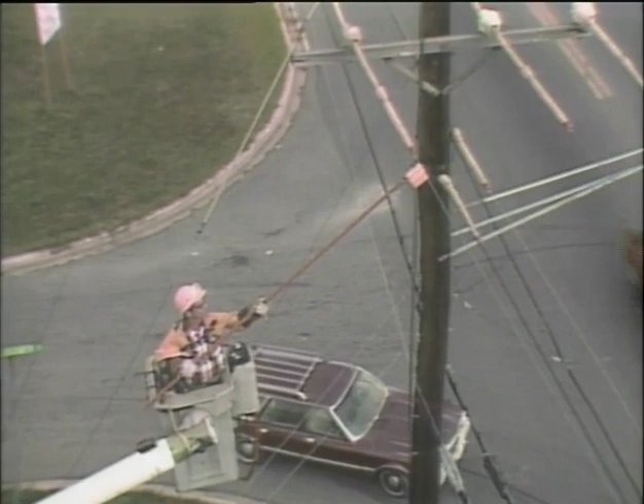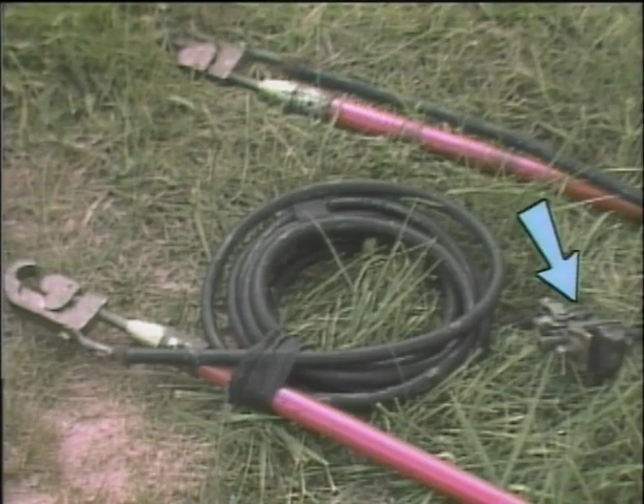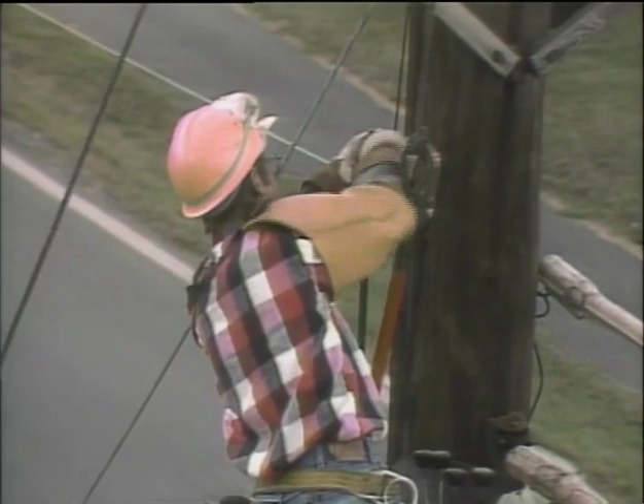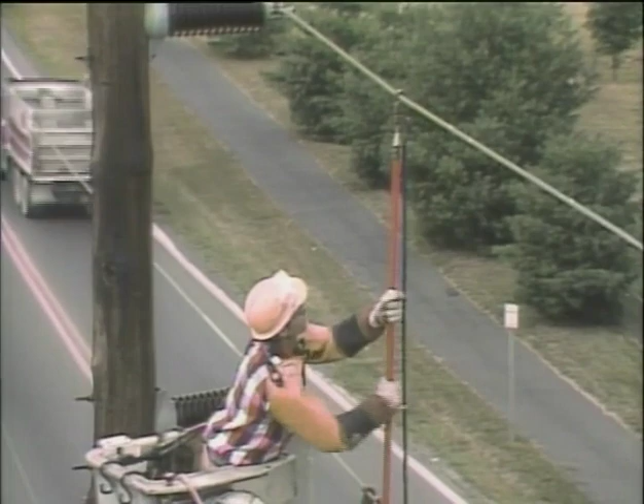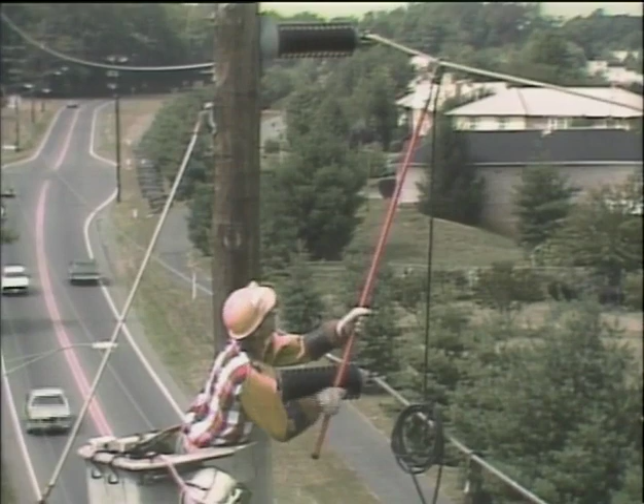Using temporary grounds helps protect the worker in case the lines should suddenly become energized. This grounding set has 3 jumper cables. Each cable has a pole-mounted clamp on one end and a single clamp on the other. To ground this circuit, all 3 lines must be connected by the cables to an established ground. The first jumper cable connects the established ground with the bottom line. The second jumper cable connects the bottom line with the middle line. And the third jumper cable connects the middle line with the top line. The jumper cables now create one electrical path to ground for all 3 lines in the circuit.